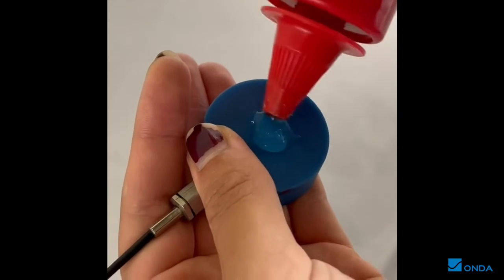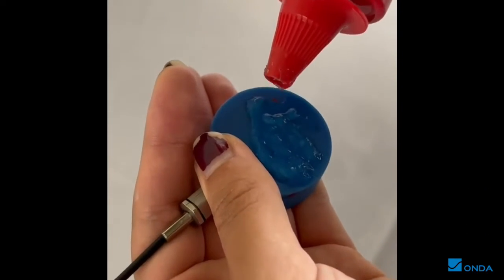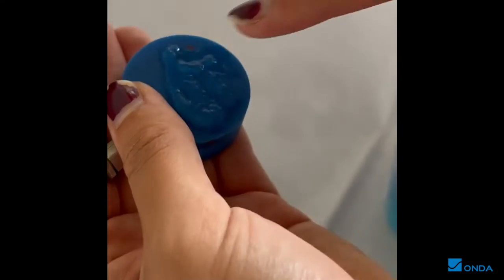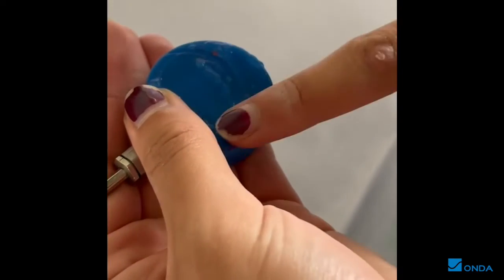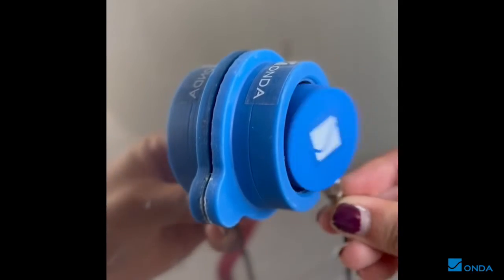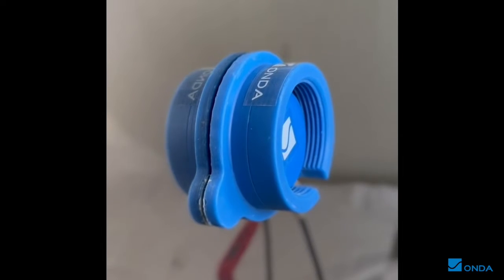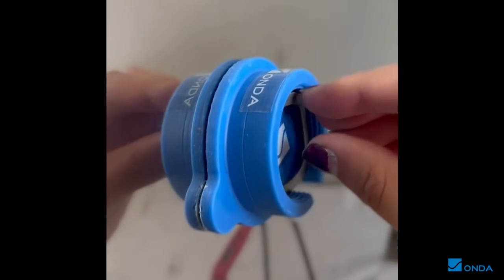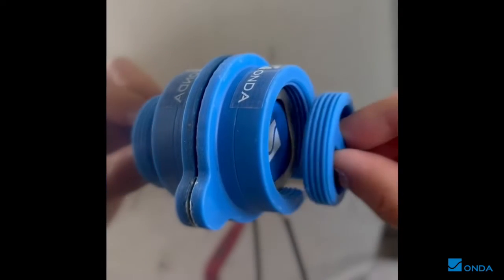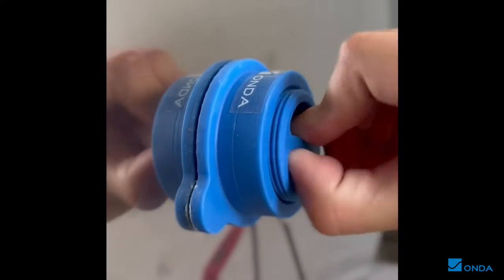Apply the coupling agent onto the face of the sensor and spread evenly. Place the sensor, spring, and locking piece into the housing. The locking piece should be securely tightened by hand.